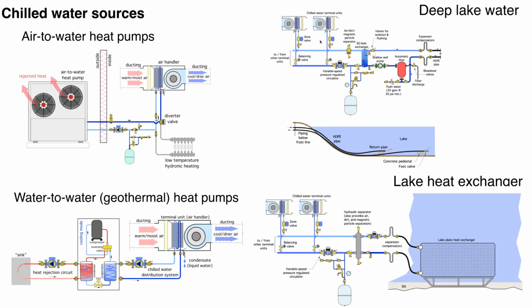They've been used in the geothermal industry as a substitute for buried tubing. They are typically made of stainless steel, and I would describe them similar to some of the older style waffle plates that were used in solar collectors. Basically, it's two steel plates that are formed to create these dimples, and that causes the flow to spread out across the plate. And then it's welded together at the perimeter. And then multiple plates are manifolded into a header system. The header system would connect to typically high density polyethylene tubing, and that would come in.